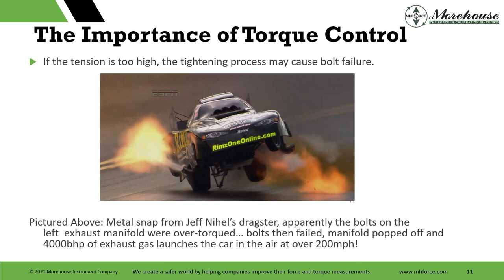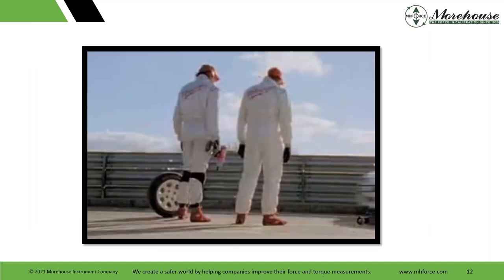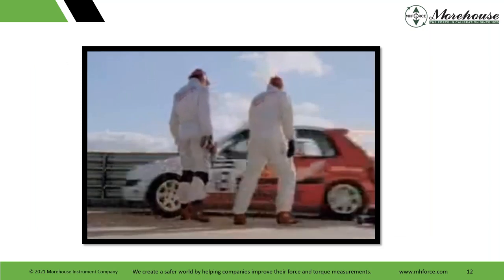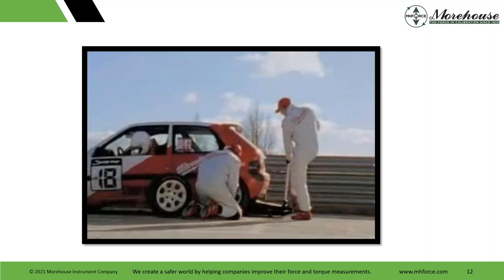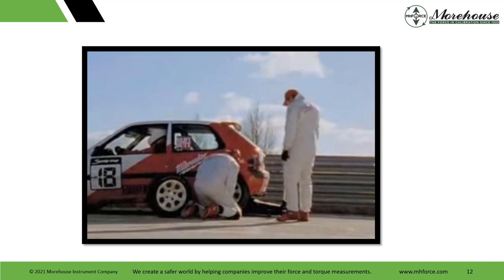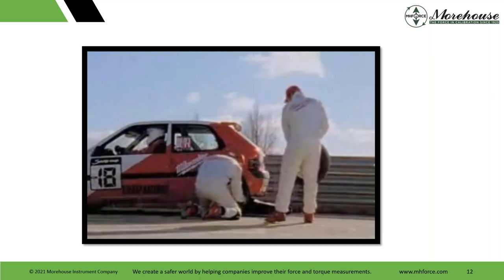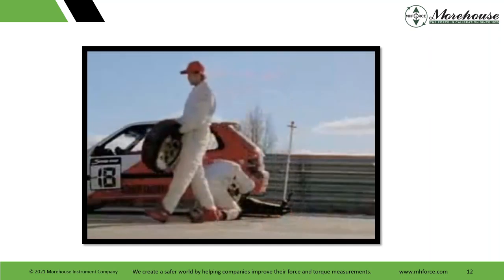We do a lot of force and torque here. Jeff Nyhiel's dragster: he's racing, bolts are over-torqued, they pop off, the left exhaust manifold pops off, and 4,000 BHP of exhaust gas launches the car in the air at over 200 miles per hour. We basically over-torqued our bolts and created a rocket. Here's a video — you do not need sound for this. It's one of my favorite videos when it comes to torque control. We have the second most accurate torque calibration machine in the world, built by NPL, better than 20 parts per million.